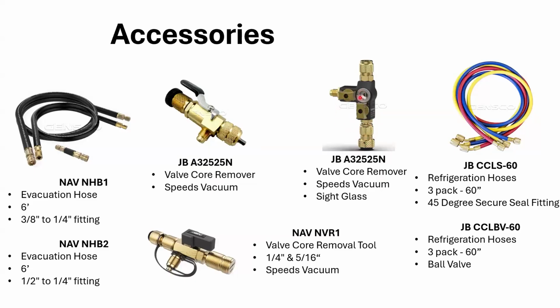Between this setup right here, removing the valve cores, getting the Schraders out of the way, and larger diameter hoses, getting up to the 3/8 or larger, you don't need a 20,000 CFM vacuum pump. You could run a 5 CFM vacuum pump and use this setup right here. Get this tool, get the Schrader out of the way, use bigger diameter hoses. It'll speed your vacuum up. It's not the CFM of the pumps. It's all this right here. There are a lot of videos that show it, and guys have done it and proved it.